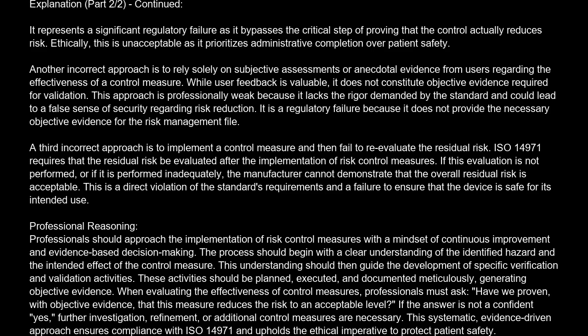A third incorrect approach is to implement a control measure and then fail to reevaluate the residual risk. ISO 14971 requires that the residual risk be evaluated after the implementation of risk control measures. If this evaluation is not performed, or if it is performed inadequately, the manufacturer cannot demonstrate that the overall residual risk is acceptable. This is a direct violation of the standard's requirements and a failure to ensure that the device is safe for its intended use.